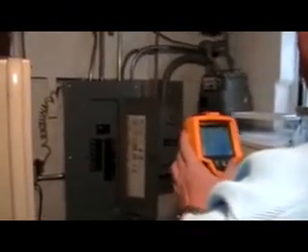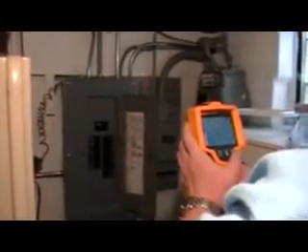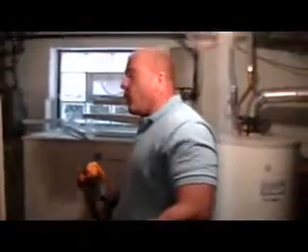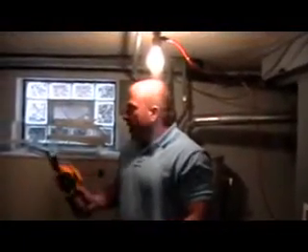What I'm finding right now is that we have one breaker that's a little warm, and that's generally not a big problem, but it could be. This is basically a picture of what you would see on your report. We'll get a little closer in when we open up the box and see what the problems are on the electrical.